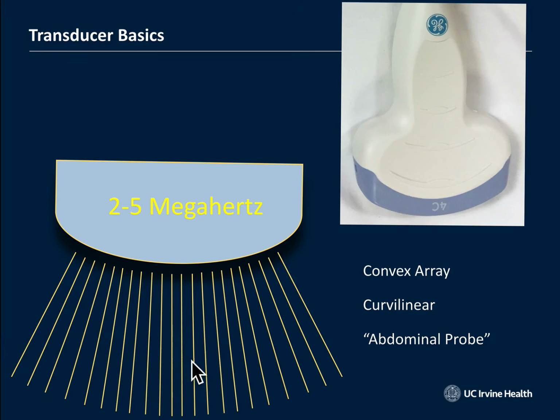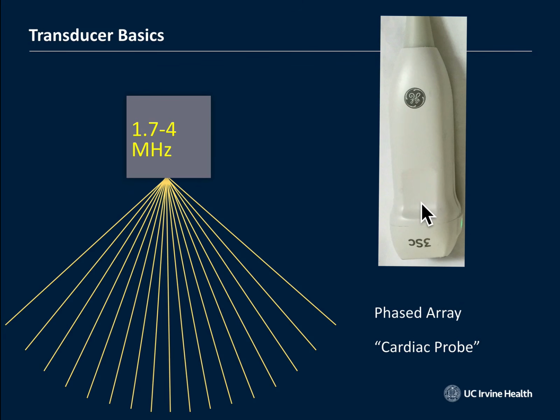Whereas down the center, dead down the center, I'm going to get the best possible lateral resolution out of this probe. You lose a little, it's not too bad. Because of all these elements here, though, you get beautiful images from this convex array transducer. Now, look at the difference, though, when you use this phased array smaller footprint transducer here. It's really good at getting between the ribs, and for that reason, you hear it called the cardiac probe sometimes. But the phased array small footprint transducer, it's got a single crystal here, and the sound is electronically steered into the body in a very wide array.